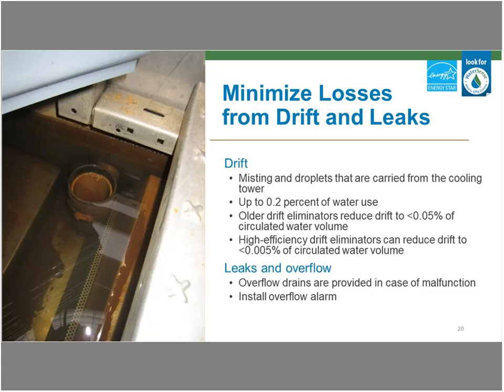The other maintenance item to be aware of is cooling tower overflow. Many towers are equipped with an overflow drain to prevent overfilling the tower basin in the event of an equipment malfunction. If the level sensor or the fill valve in the tower fails, water then flows to the overflow drain and can happen without facility staff really realizing it. So the photo on the slide is from a tower basin where the fill valve controlling the makeup was stuck partially open.